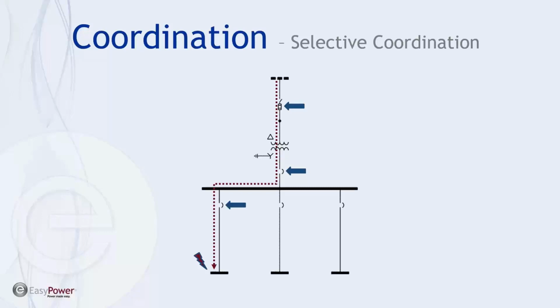And so the problem is, if the main breaker trips, then all of the loads on the distribution panel will go down. If the primary fuse is tripped, then the whole plant goes down, or the whole substation goes down, and it may be unnecessary, or have been unnecessary, had we properly coordinated the system. So again, what we're trying to do is to isolate the fault and make sure that this device clears the fault before the 2 upper protective devices are activated.